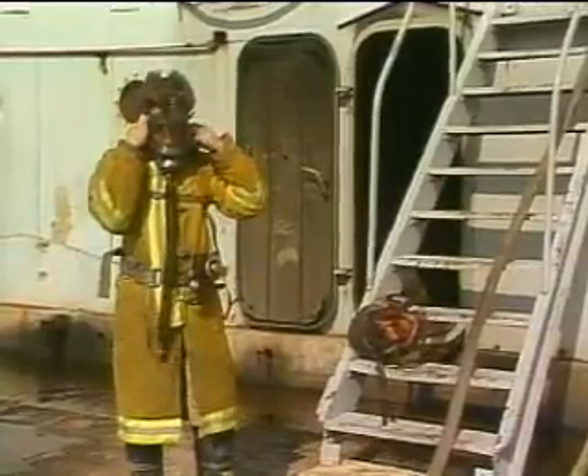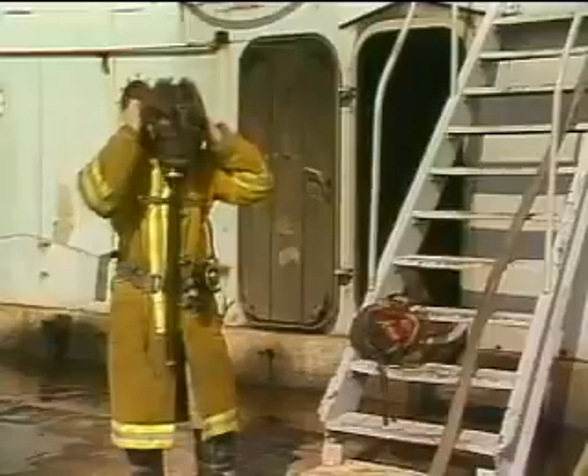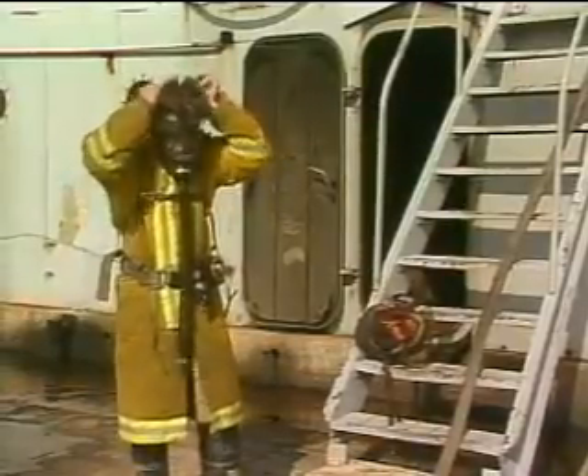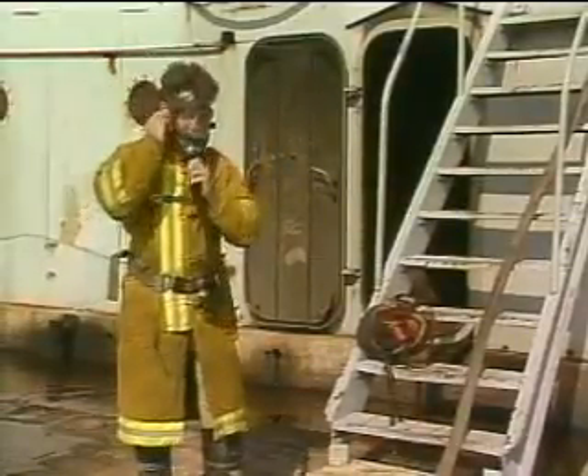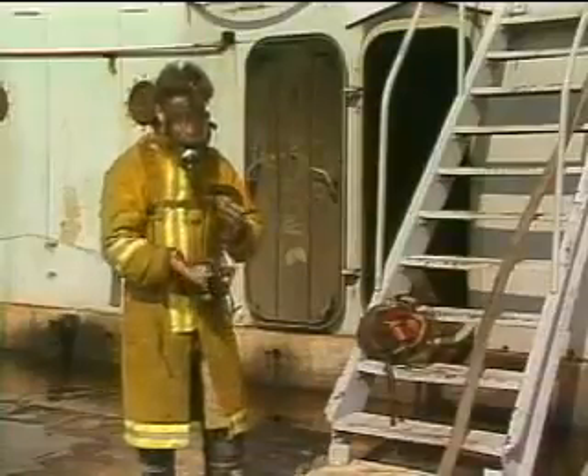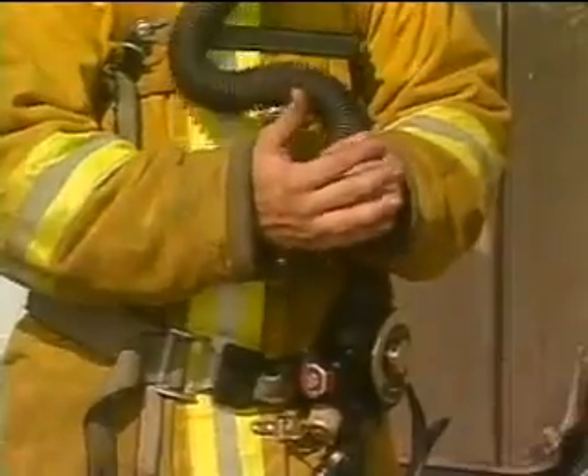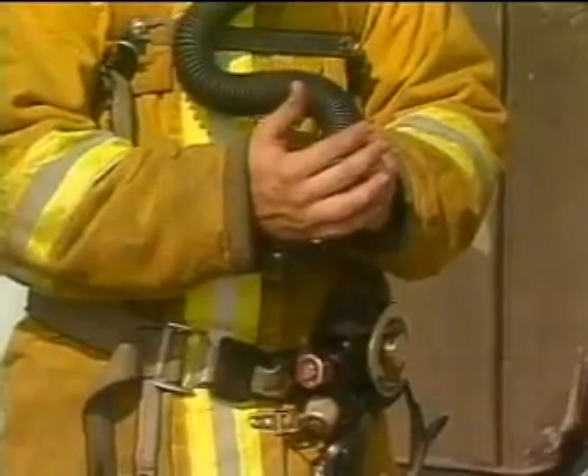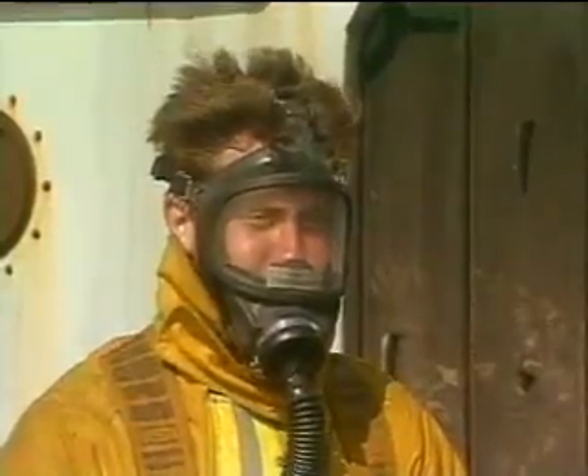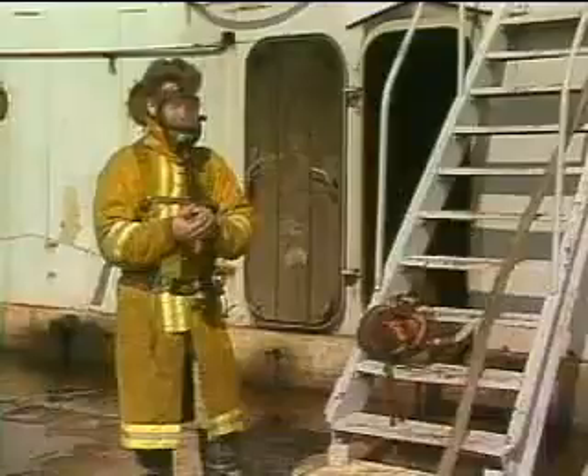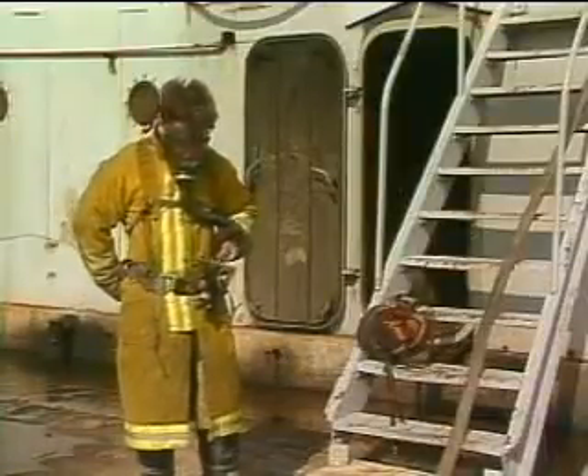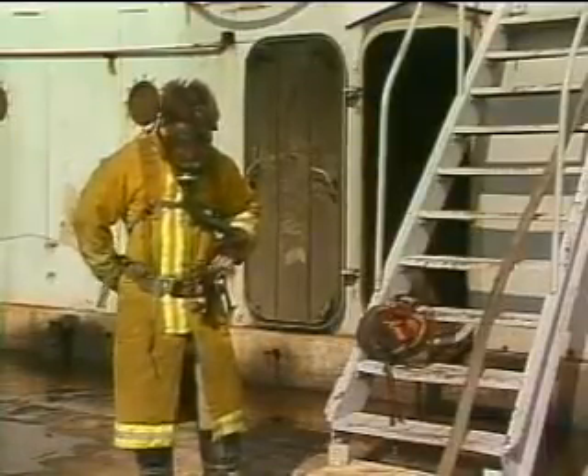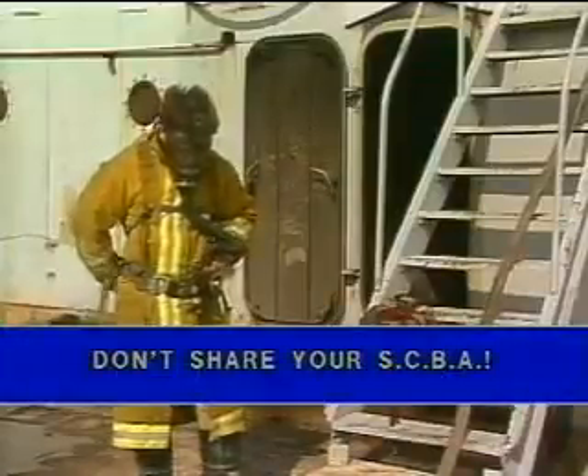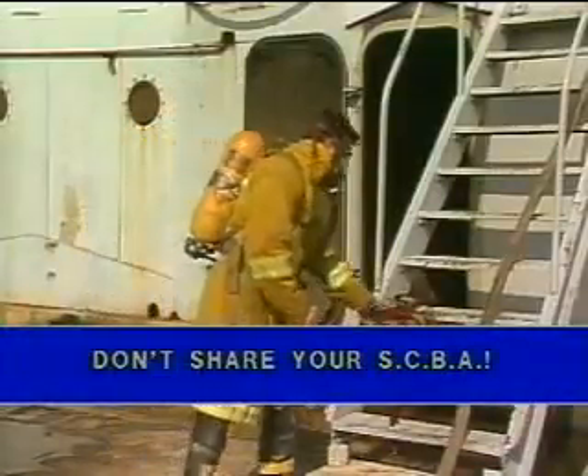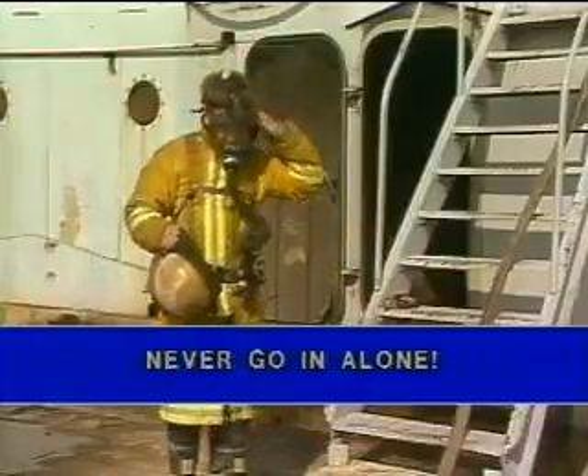Be aware of some precautions. Make sure the apparatus fits properly. If you have a beard or long sideburns, you won't get a proper seal. If you're attempting to rescue someone, don't share your SCBA. And remember, rescue is a team effort. Never go in alone.